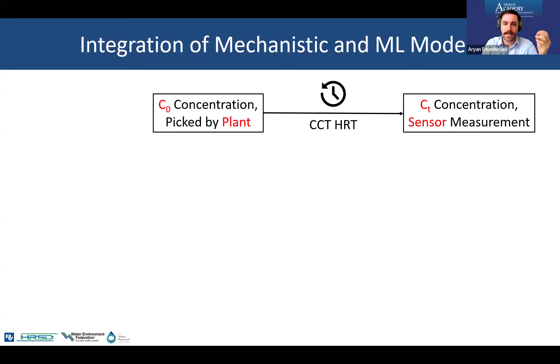As I mentioned, the data we had included the initial chlorine concentrations picked by the plant, the hydraulic retention time values in the chlorine contact tanks, and the chlorine measurements at time t. Using this parameter fitting approach, we could back-calculate the C0 concentration that needed to be chosen given the chlorine decay function based on our CT measurement.